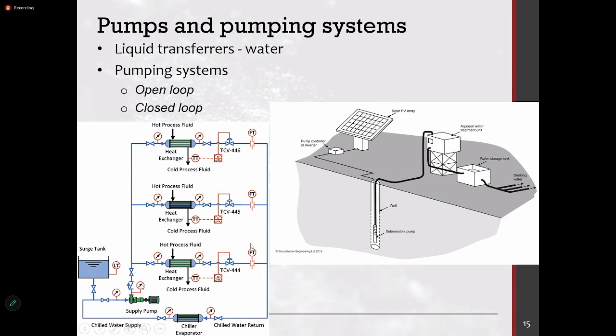So once the pressure increases, you install a VSD plus a pressure sensor to monitor the pressure, and you have a set point for the pressure. So depending on the pressure, you reduce the RPM of the motor. Then the pressure comes back to your set point, and we circulate water in the same system. Similarly, once this closes up, again the pressure increases, then the VSD will reduce the RPM further and reduce the water flow rate. So this is a variable water flow rate. Similarly, this can be done even for a condenser cooling tower water flow rate as well.